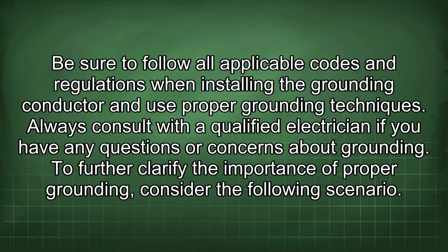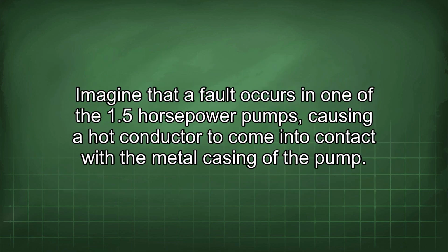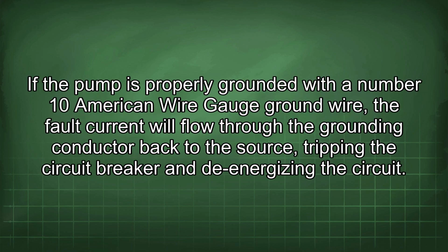To further clarify the importance of proper grounding, consider the following scenario. Imagine that a fault occurs in one of the 1.5 horsepower pumps, causing a hot conductor to come into contact with the metal casing of the pump. If the pump is properly grounded with the number 10 American wire gauge ground wire, the fault current will flow through the grounding conductor back to the source, tripping the circuit breaker and de-energizing the circuit.